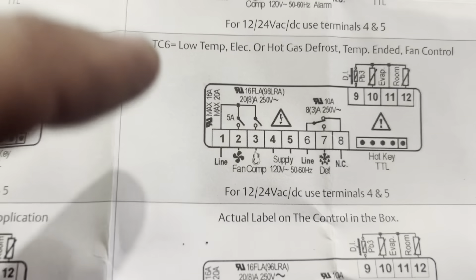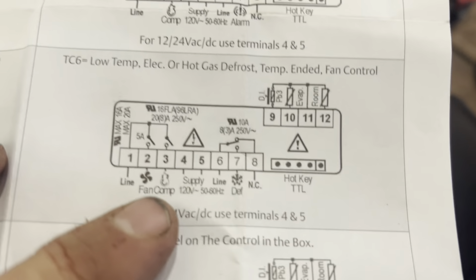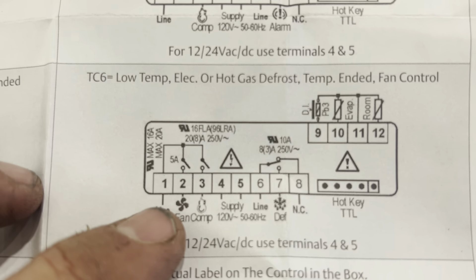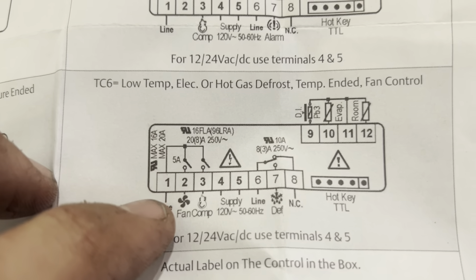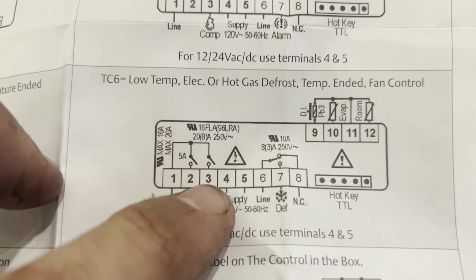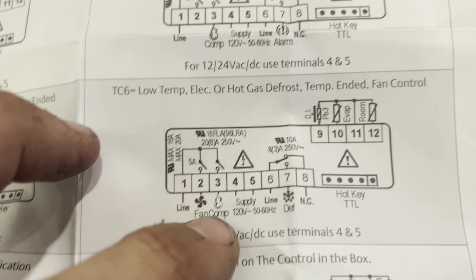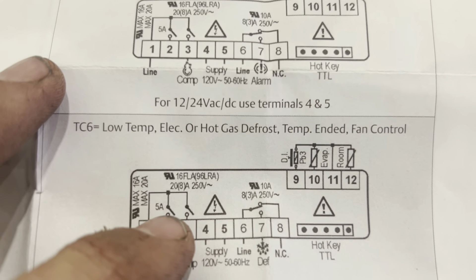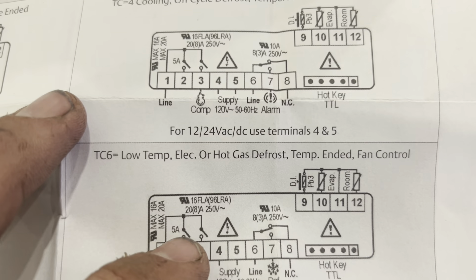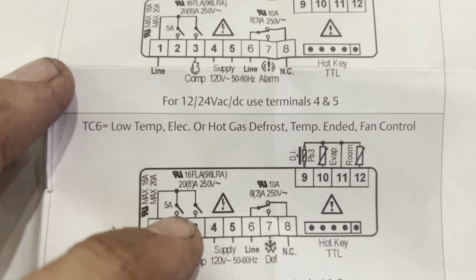It's almost identical. We're going to go TC6 — low temp electric defrost temperature with fan control. The only difference is: you've got your line in, your supply powering the clock, then you've got your line in running to just the cooling circuit. You can see they're opposite — the defrost circuit. Fan and compressor go there, and you do need to mind where the five-amp switch is, because the fan has to be on the five-amp switch.